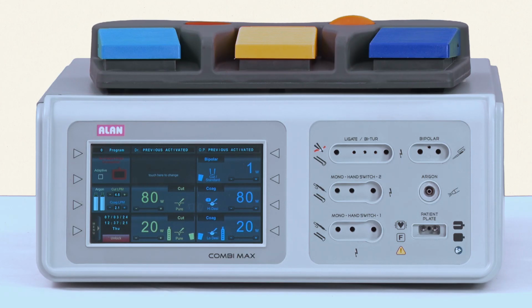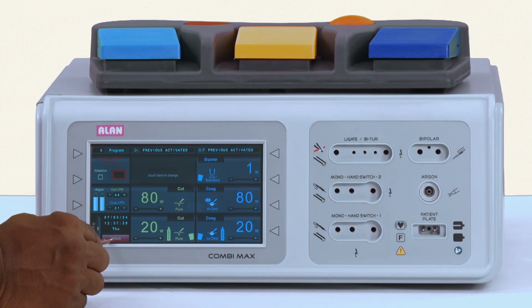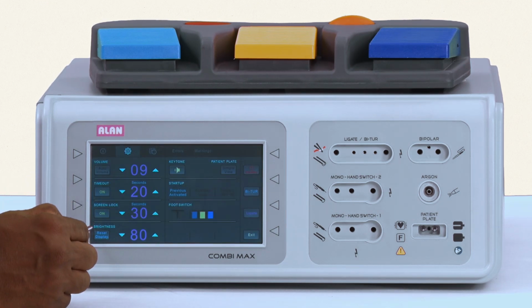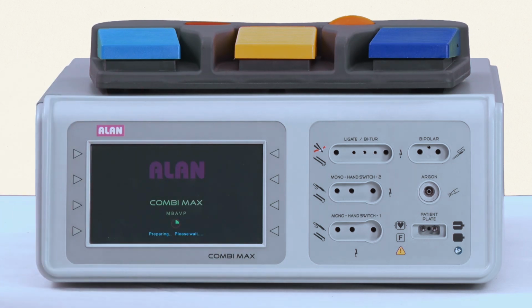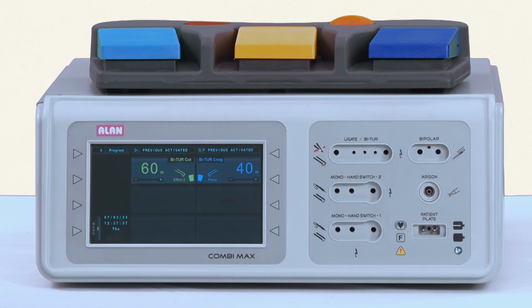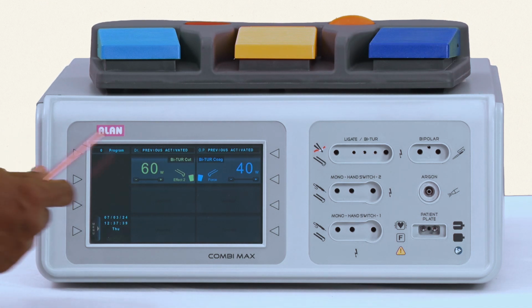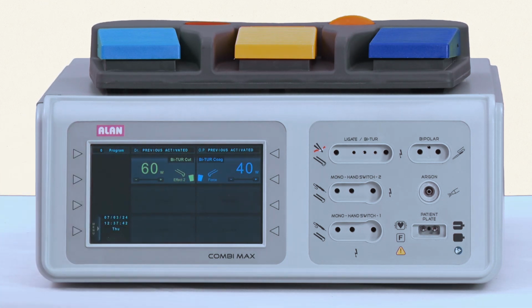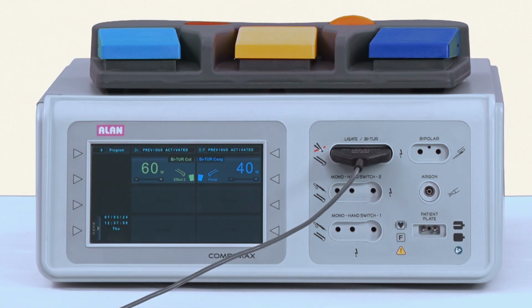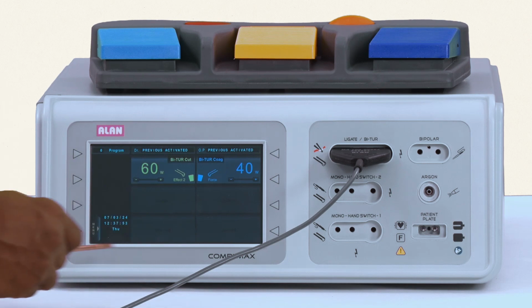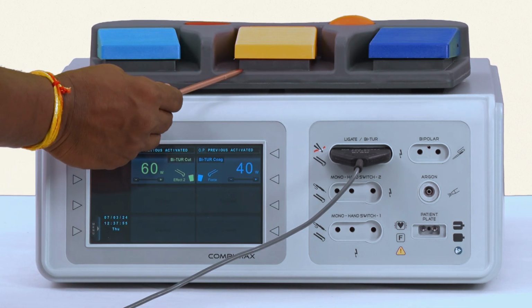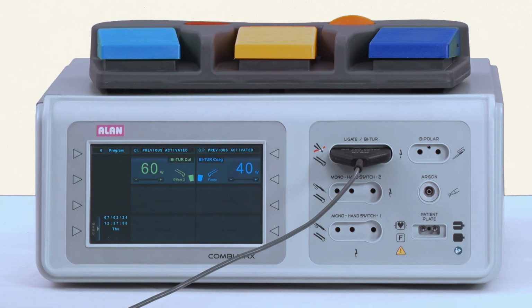Use Combi Max in bipolar saline resection surgeries. You must be in the BiTUR window. To access it, unlock the screen, go to menu, click on BiTUR. Now you are in the BiTUR window screen. Choose the modes and wattages as per your surgical requirement. Connect the instrument here. Now the unit is ready to deliver the power. Choose the yellow pedal for cutting and the blue pedal for coagulation.